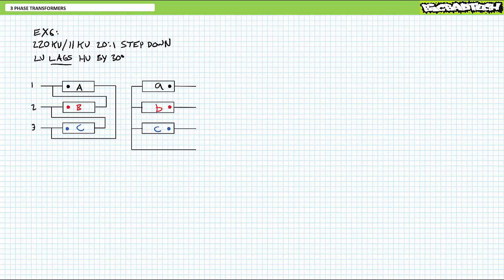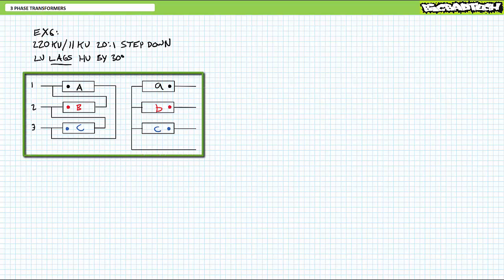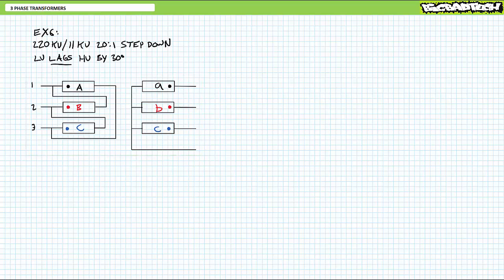All right, let's try another example, only this time let's go in an opposite direction. Consider a three-phase transformer with a 20 to 1 turns ratio, designed to step down 220 kilovolts to 11 kilovolts with the following simplified connection diagram, and we know the low-voltage secondary side lags the high-voltage primary side by 30 degrees. Can you form the nomenclature and draw the displacement diagram given the information you have in front of you?